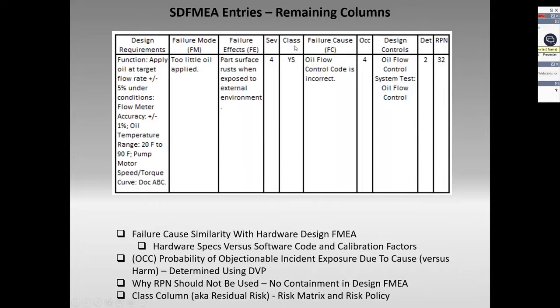It's basically, when I look at the design as it currently is now, what level of risk will the user of my software be exposed to? And it's based on two numbers: the severity of harm and the occurrence, which is the probability of this failure here of too little oil because of the way I wrote the control code.